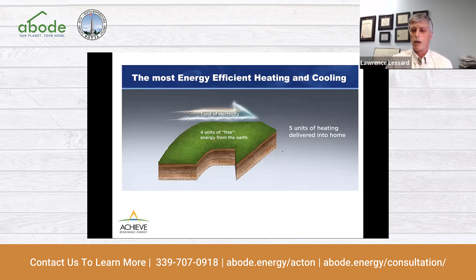So if you picture the farmer with his combine harvesting the wheat, he's using diesel fuel to power the combine, but he's getting all that wheat in. What we get is heat from the ground, and that 1 kilowatt of electricity will let us harvest 4 kilowatts of thermal energy. And then it's just a quirk of the way heat pumps work that the waste heat from the equipment dumps to the hot side of the machine. So you do get the 1 kilowatt of thermal energy out of the electricity also, for a total of 5. In the air conditioning mode, we're pumping heat into the ground, and we're also pumping the heat from the equipment into the ground. But the ground source heat pumps are so efficient at cooling that extra overhead doesn't really matter.